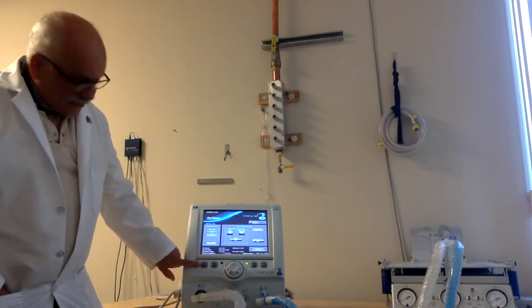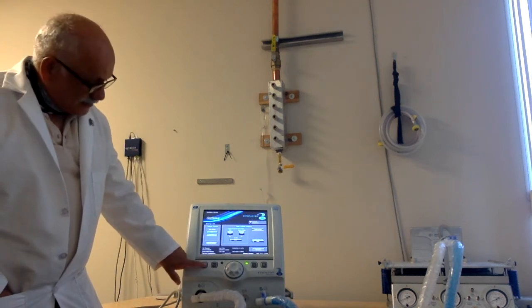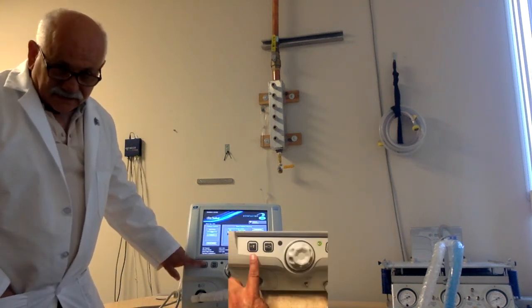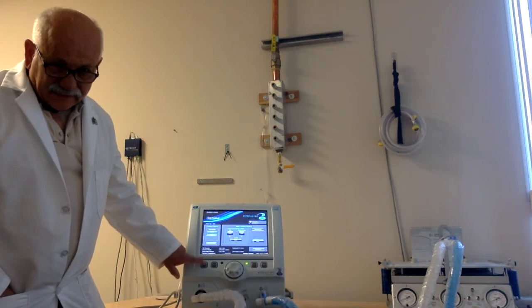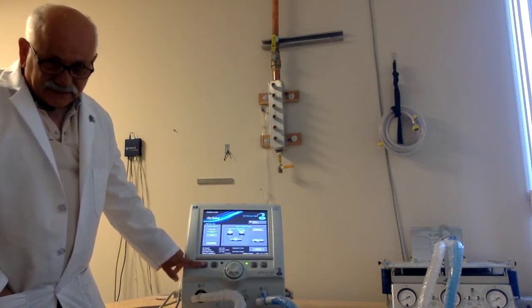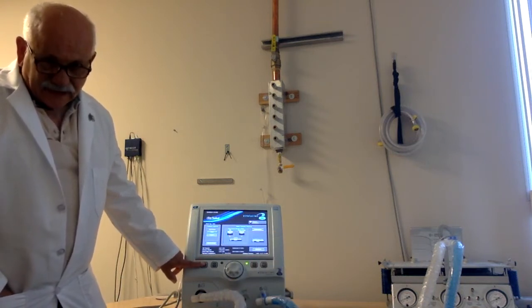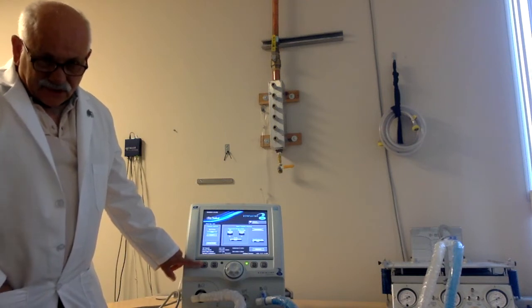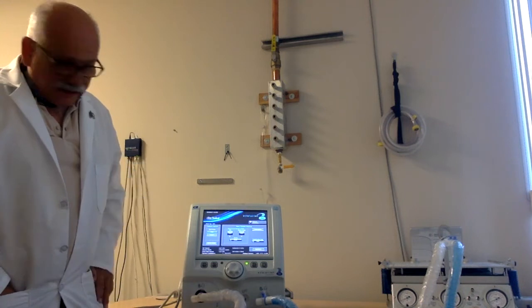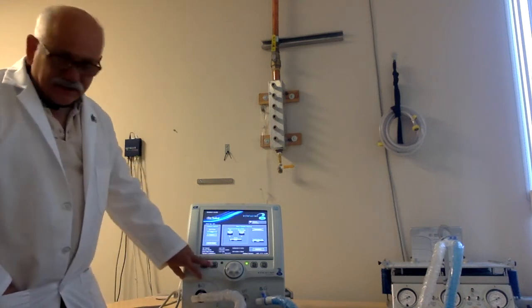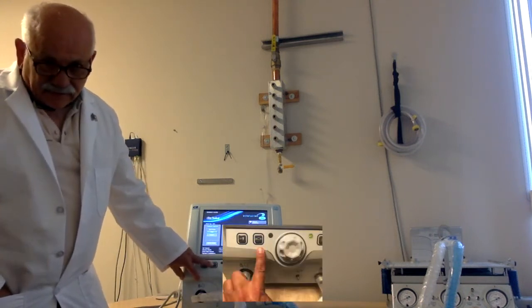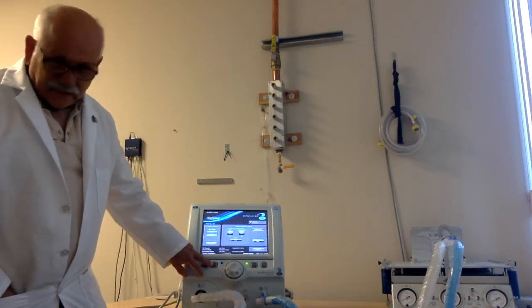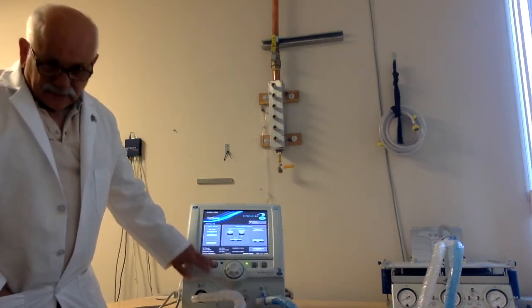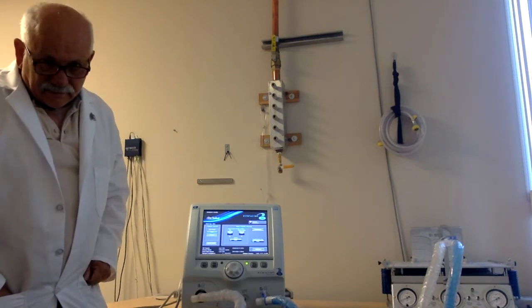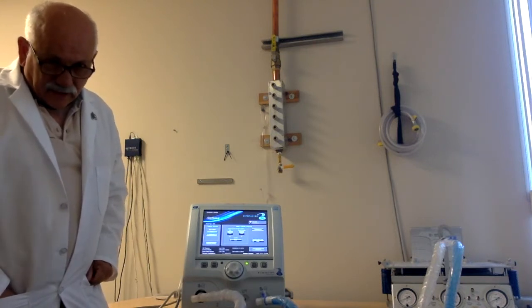Here we have the ability to increase oxygen by pressing this. And this ventilator also allows you to, in the neonatal area, or even in the case of COPD, where oxygen has a high level of toxicity, set the level of oxygen increase, the step increase in oxygen. Here you have a manual inflation button, so every time you push this, it will deliver a breath. This is very useful in hyperoxygenation.